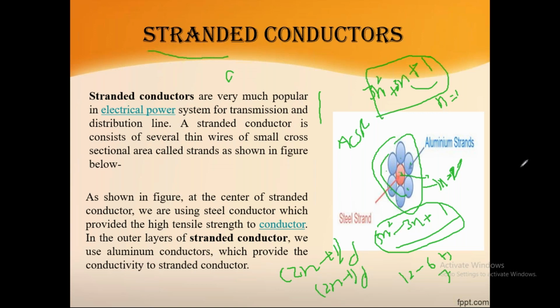You can use any equation, but most standard books use this formula: 3n square minus 3n plus 1, and 2n minus 1 into d. This means they consider the center conductor as also one of the layers, so it has two layers: one is red color, the steel strand, and the aluminum strand. This is the advantage of stranded conductors and how we calculate the number of strands in a conductor.